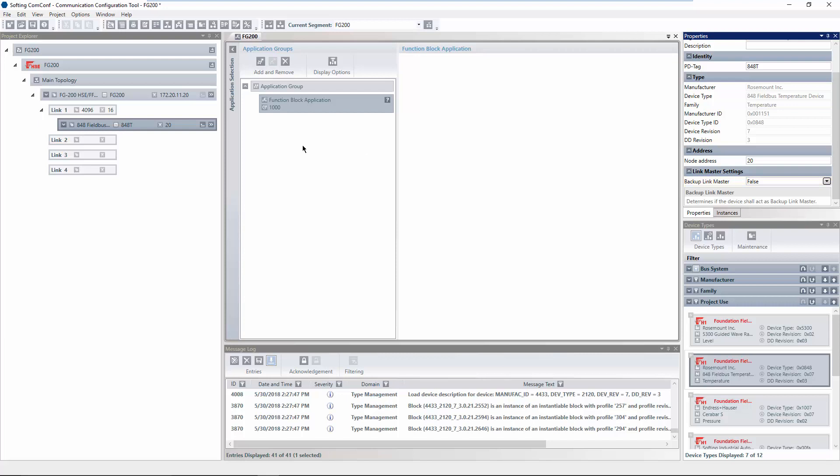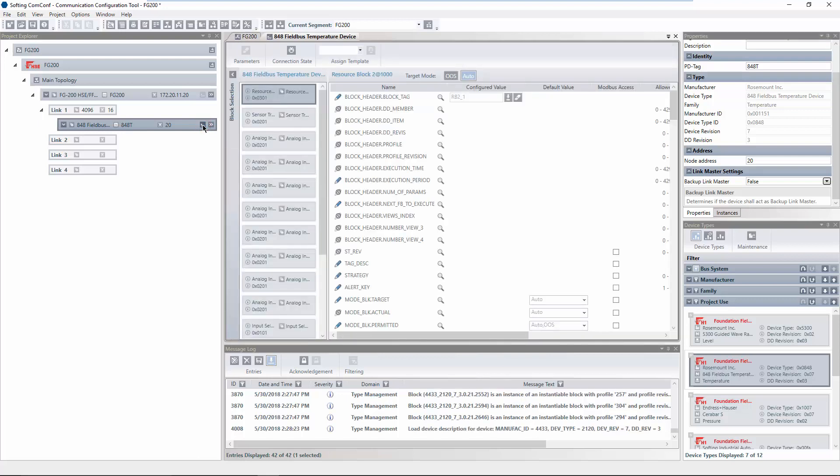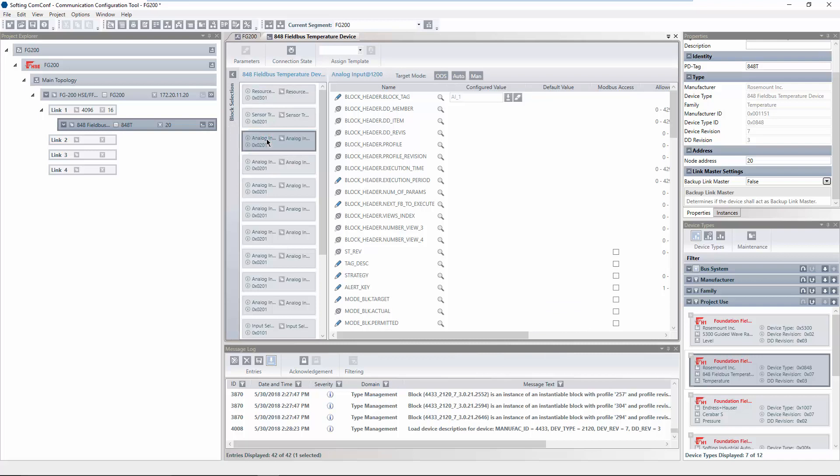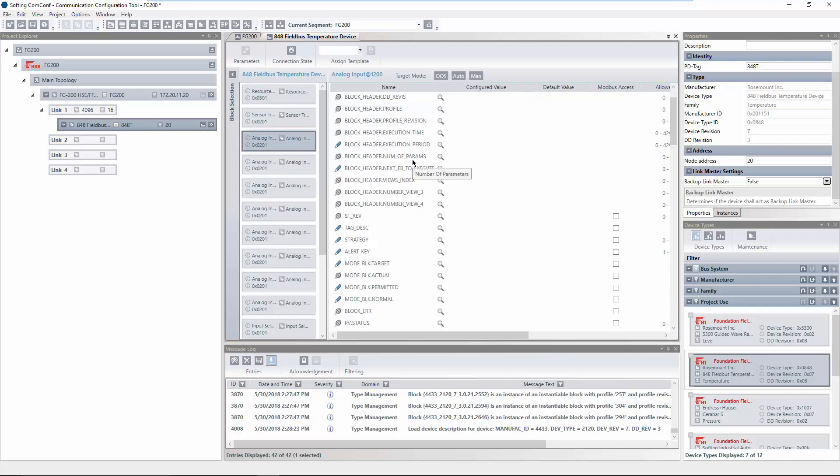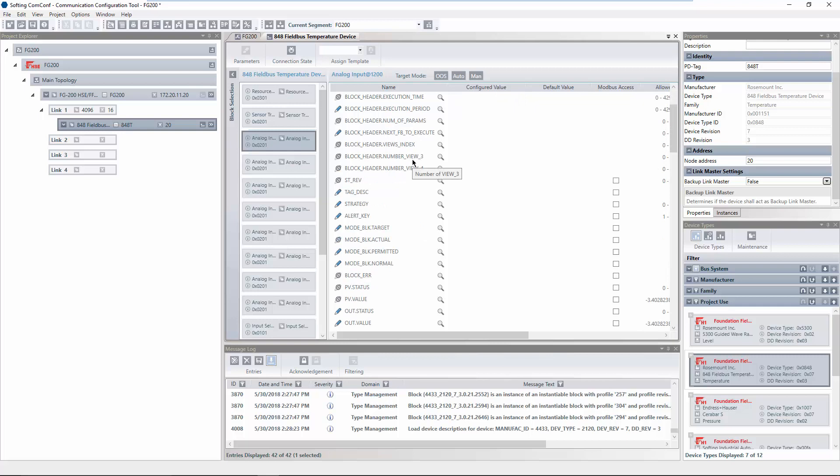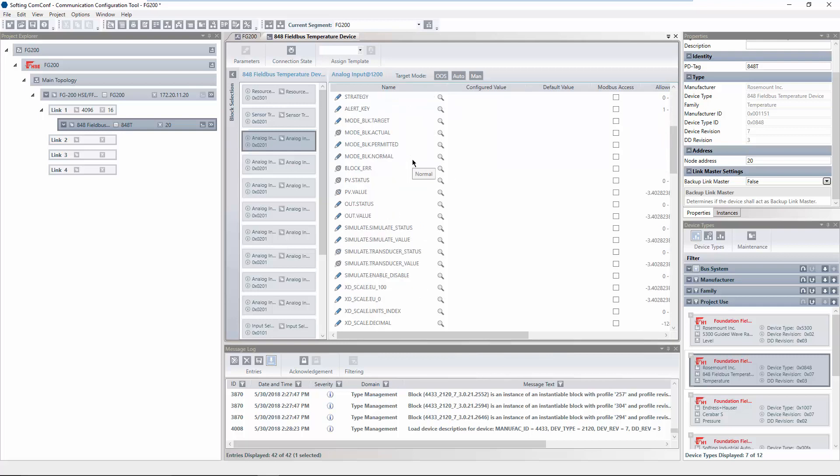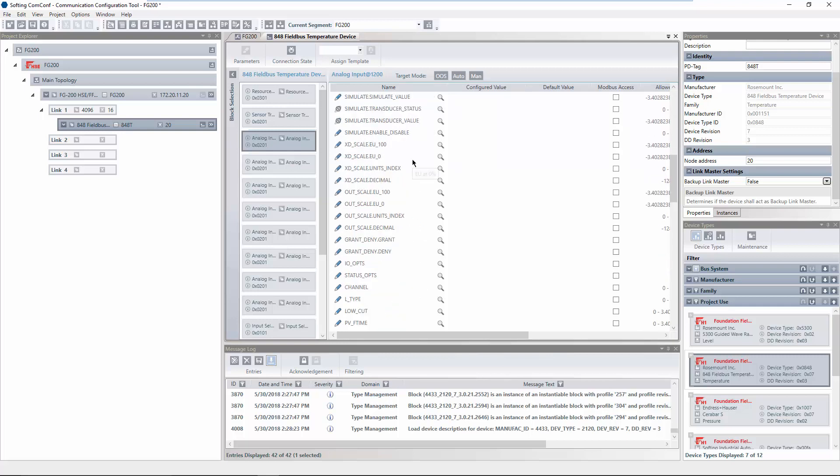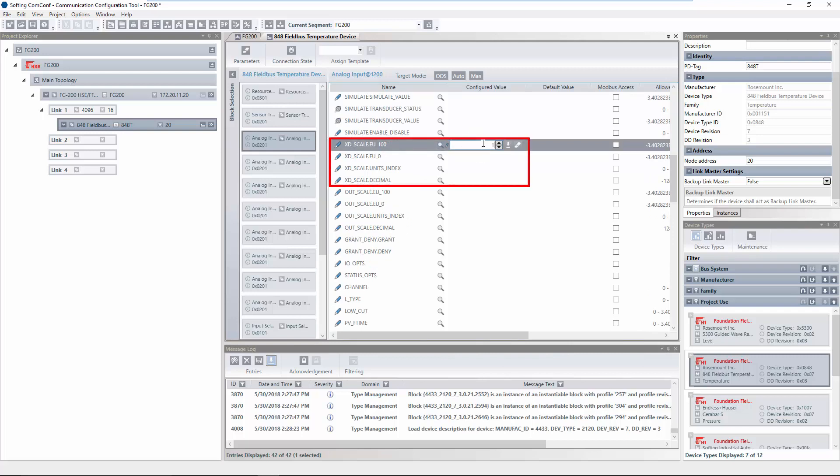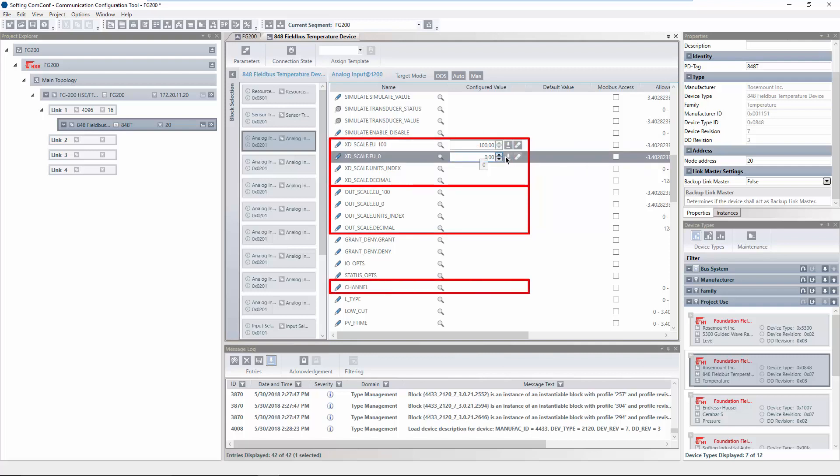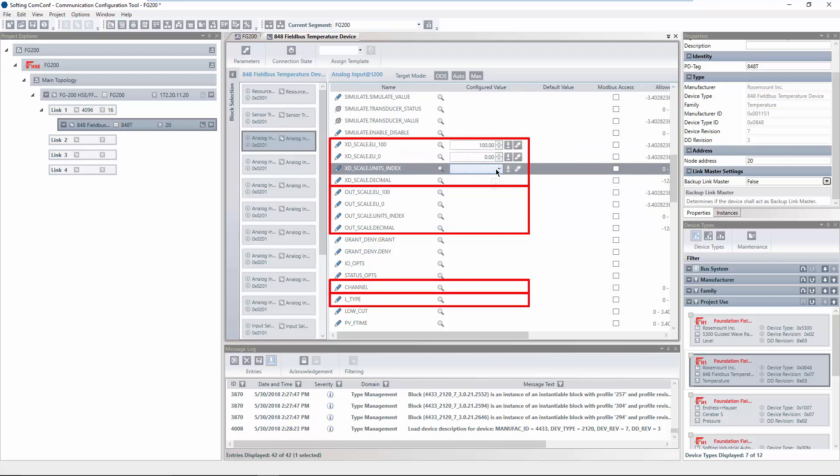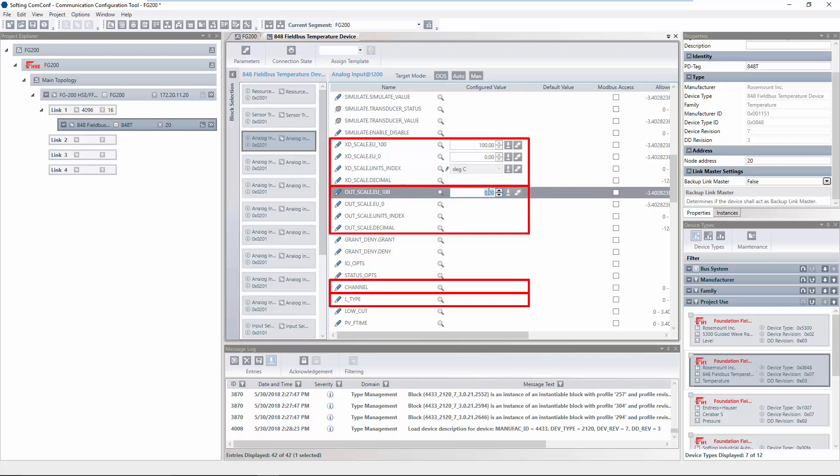In the following, an analog input block will be configured to access its process value via Modbus. Click on Edit Configuration Parameters of the H1 device and select the corresponding block. First, we will configure the parameters XDScale, OutScale, Channel and LType to provide the temperature value of the H1 device via the output parameter of the block.